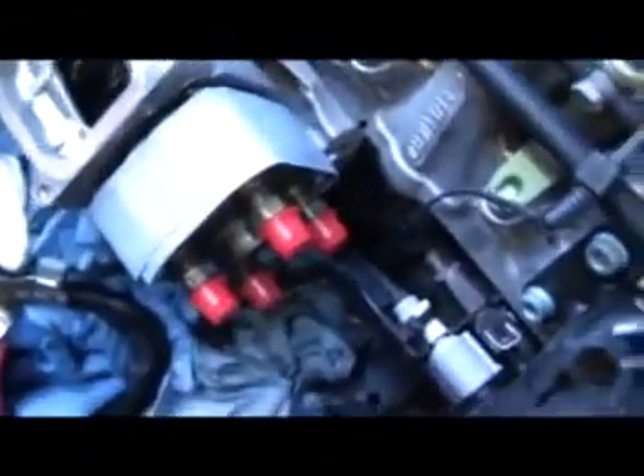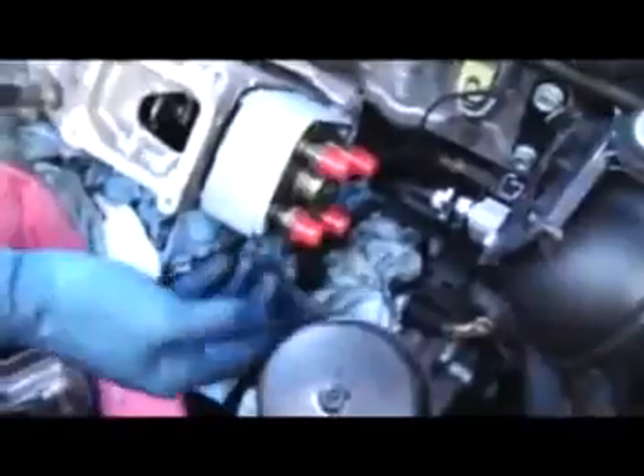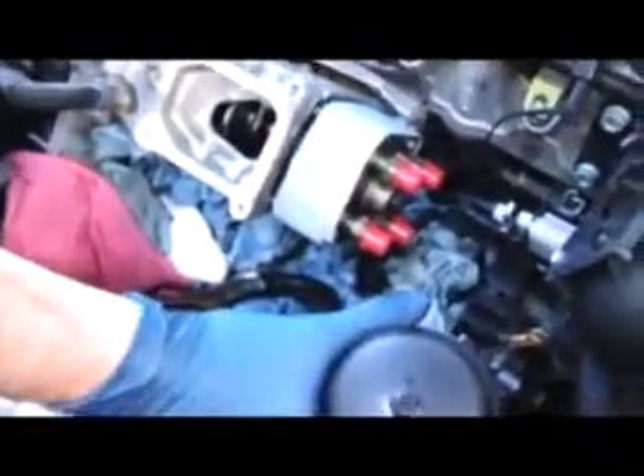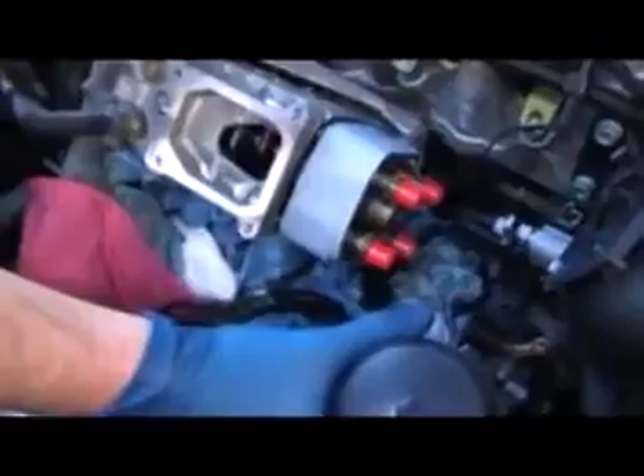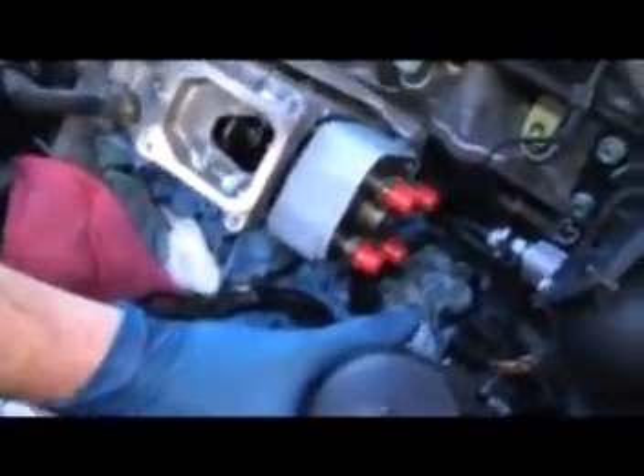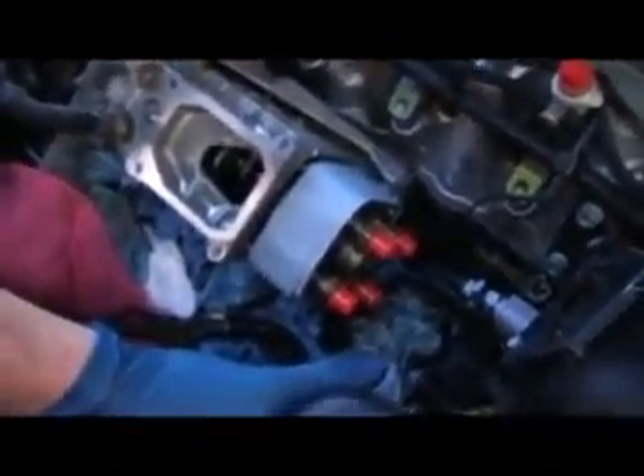So we've got this new seal here, and I like to put a little bit of grease on it. I just use a small amount of this axle grease and just kind of smear it between my fingers and just run the seal through it. This will keep it from twisting over in the groove, and also make it to where when you pull the pump head back into the body of the pump, the O-ring will slide rather than catch and shave. You can actually shave a corner off the side of the O-ring if you don't have any sort of lubrication on the O-ring. Mm-hmm.